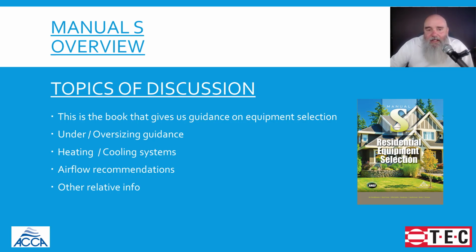And what ends up happening is someone will do an accurate load calculation. They'll come up with a BTU loss or gain that makes them feel uncomfortable. And it has a little bit more to do with air conditioning sizing than heating sizing, but let's just stick with air conditioning for the explanation right now. What ends up happening is the designer, or specifically the word practitioner is used in the ACCA design series, the practitioner ends up gaming the design temperature because they want to inflate the size of the equipment.